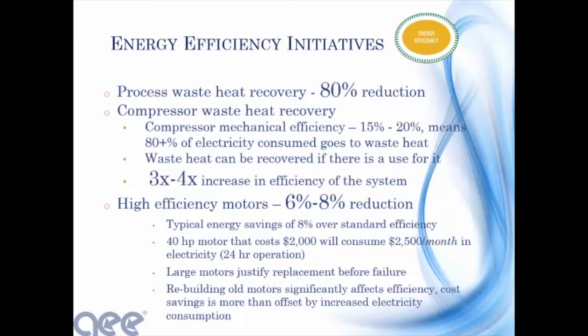So if you have a use for that heat, like with the CHP, you've got to have a sink. But if you have a use for that heat and can capture it, you can get a very high percentage of that waste heat. And then that whole process of your air compressor, instead of being 15 to 20% efficient, you can get up to 70, 80% efficiency. So we're in the midst of that right now. We have several projects underway that we're scoping out. Hopefully we'll get them implemented next year to take advantage of the waste heat.